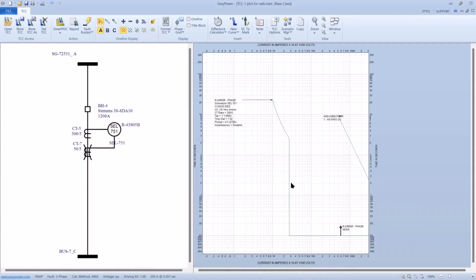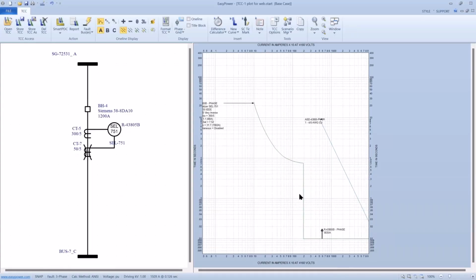So let's see how that applies to my plot. Okay, it allows me to bring it. What I'm talking about is we still get the same trip time, but we're opening up the section above it to allow other relays to be put into place for coordination purposes. So overall, this is not a bad place to start, and I reserve the right to make changes as we go forward.